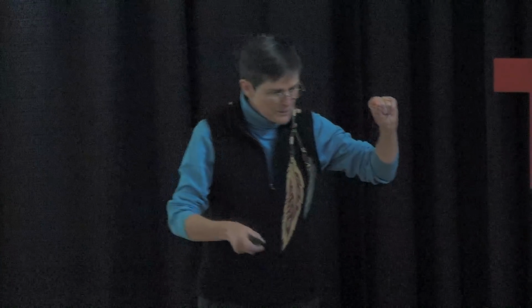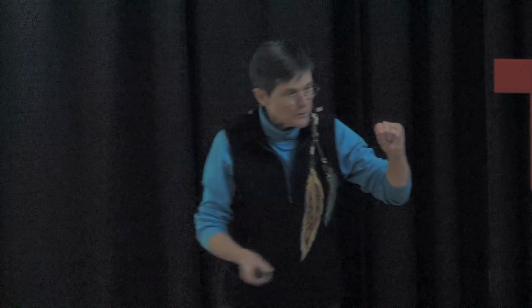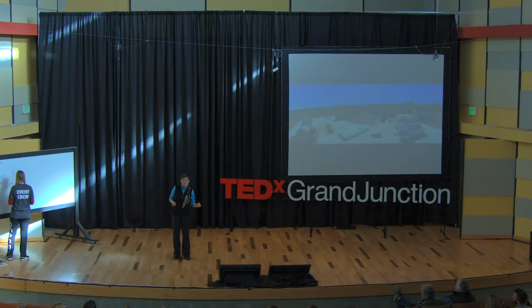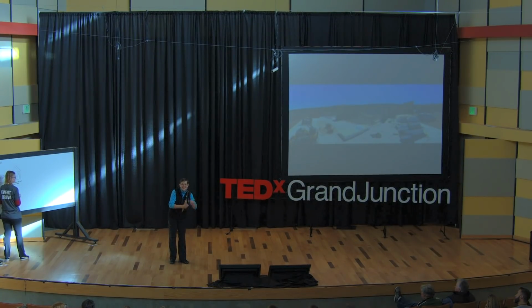There is nothing quite like pulling up to your building site and seeing the contractor's pickup truck jumping the generator. It would run for 2 hours, it'd be dead. Jump it, run for 2 hours, it would be dead. As it turns out, that backup generator was a true backup generator. You have to have it hooked into the system so it recharges that little tiny battery. It wasn't recommended for off-grid application, and because of how we used it, it voided the warranty.